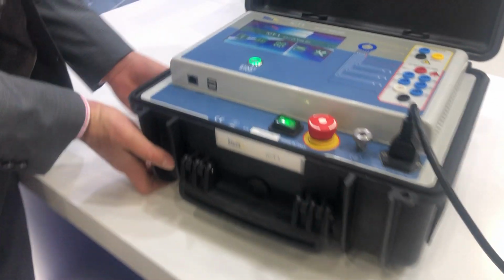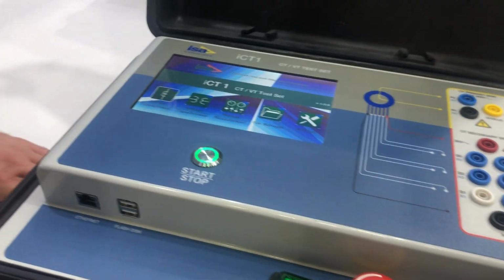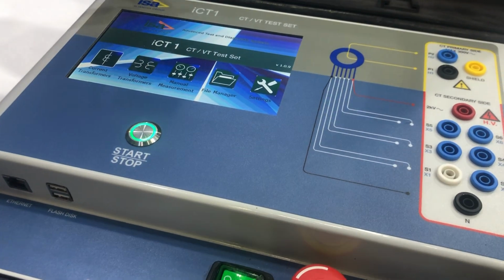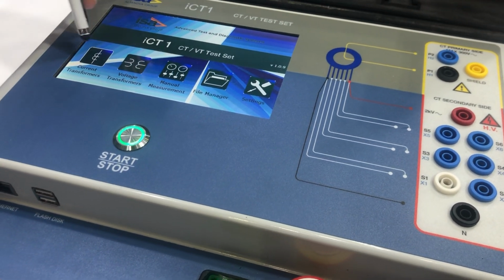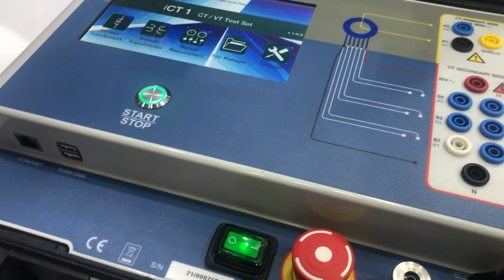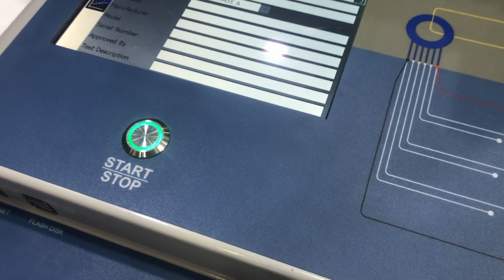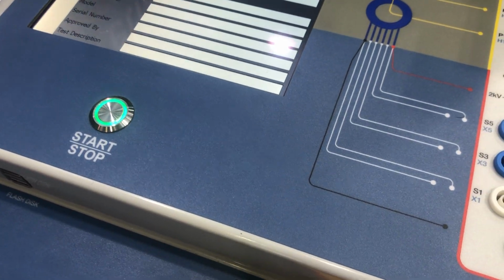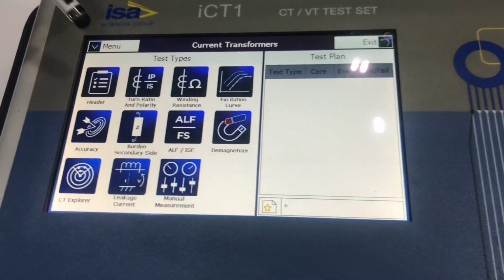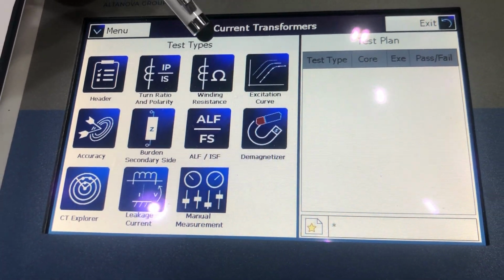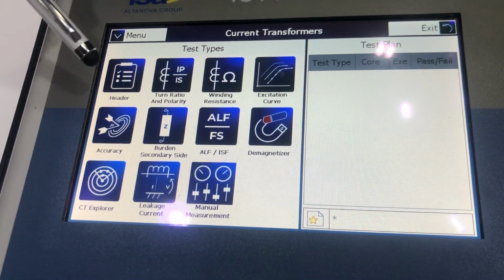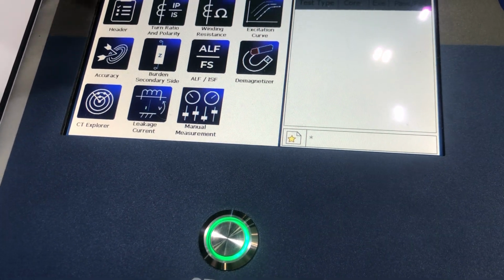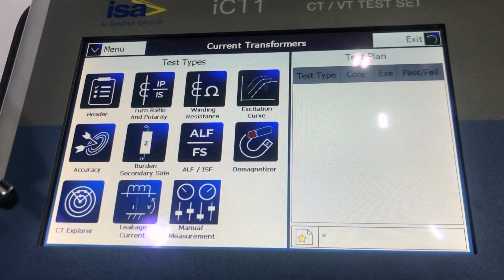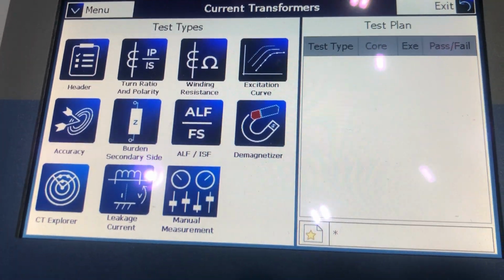Moving on, this is one of the latest developments from ISA. So this is the ICT1. The ICT1 is a tester of current and voltage transformers. It is a touchscreen device. So when I press current transformers and go test, we can see all the tests which can be done. So these are turn and ratio and polarity, winding resistance, excitation curve, accuracy, burden, ALF, ISF, demagnetizer, and when you don't have a nameplate for the transformer, a CT explorer, as well as the leakage current.